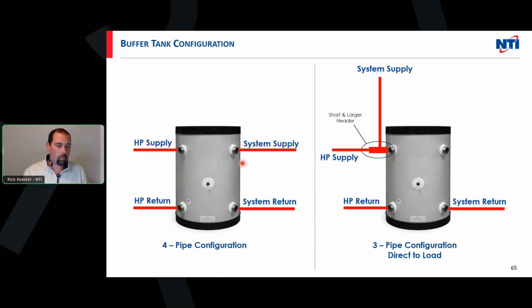And that's it. And then both of these flows from the heat pump versus the system could be 4 GPM to 9 GPM, could be 20 GPM to 9 GPM. It doesn't matter. They're going to work independently. We have some good hydraulic separation. One of the great features of a buffer tank. It's also some extra protection there, depending on the volume of this tank. It helps with defrost cycles. One of my favorite configurations, right?